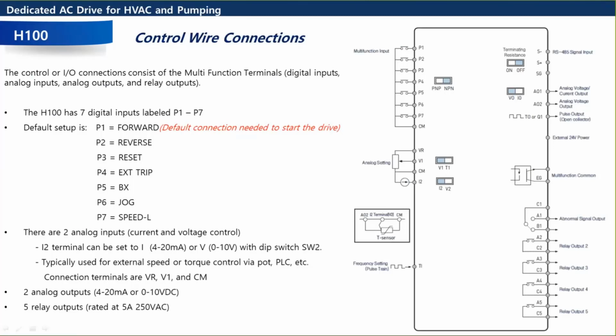So the digital inputs, we have 7 of them, P1 through P7. All the defaults are here: forward, reverse, reset, external trip, and so on. We have 2 analog inputs. We have a current one and a voltage one, and then the second current one, we could actually flip a switch and change it to a voltage, so we could run 2 voltage analog inputs. So those are typically going to be connected to your BAS system, your PLC, transducer perhaps, or a speed pot, items like that. We have 2 analog outputs, so all the outputs are on the right side of this drawing.